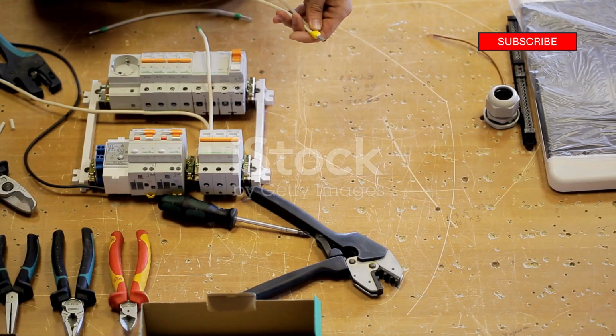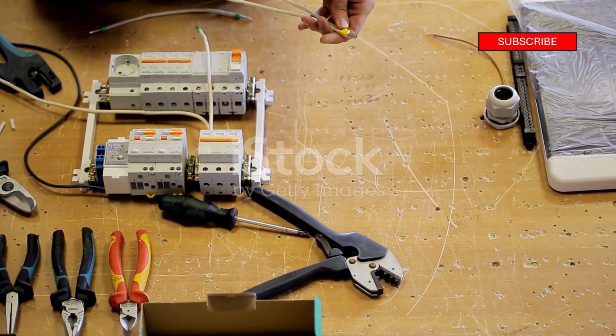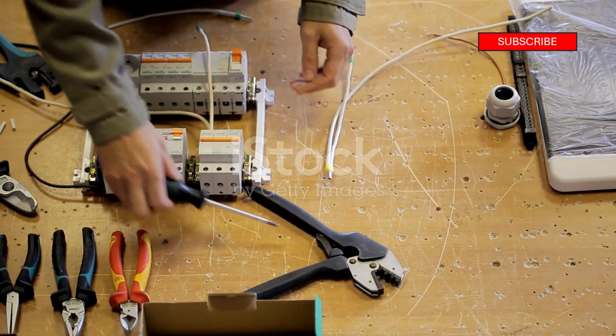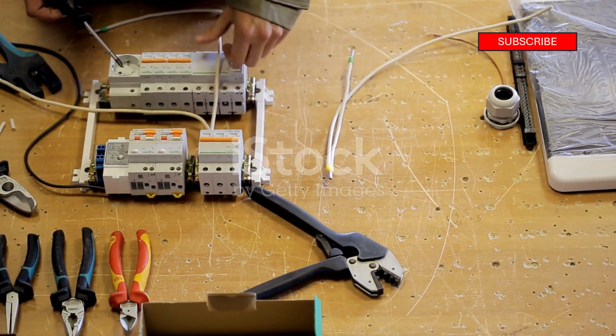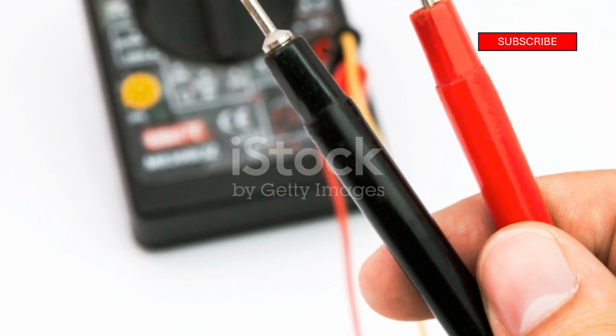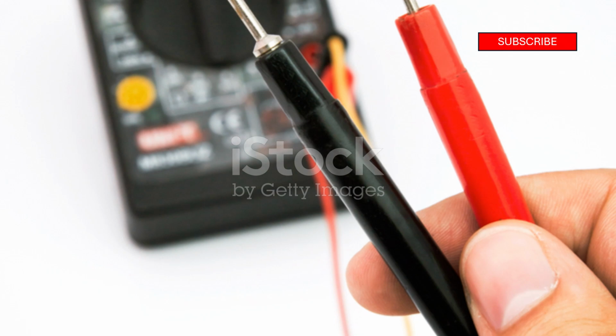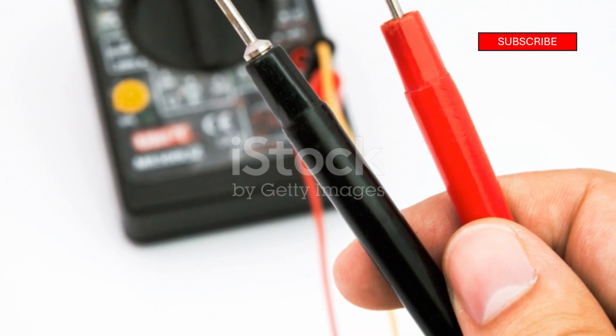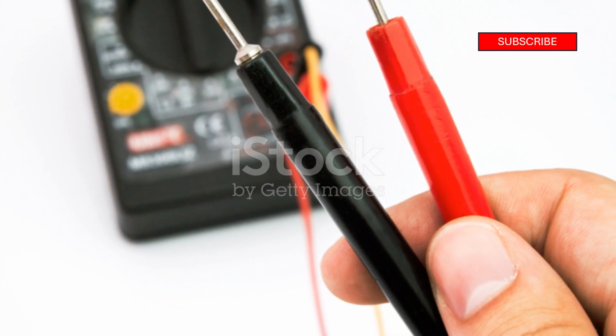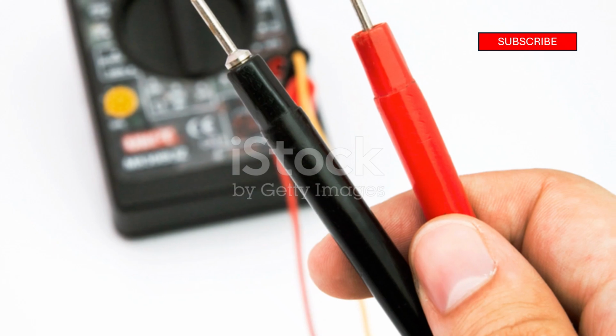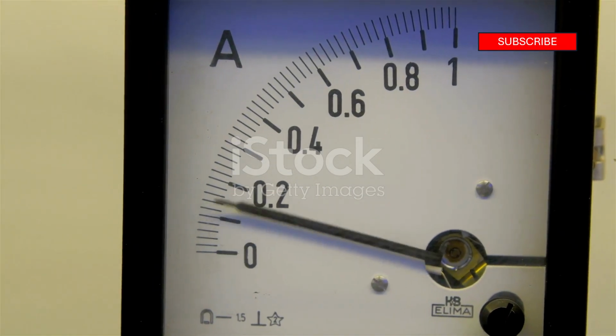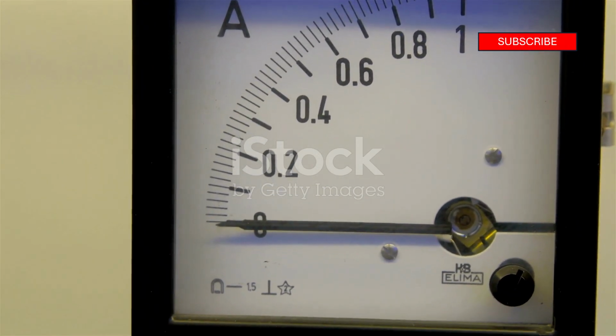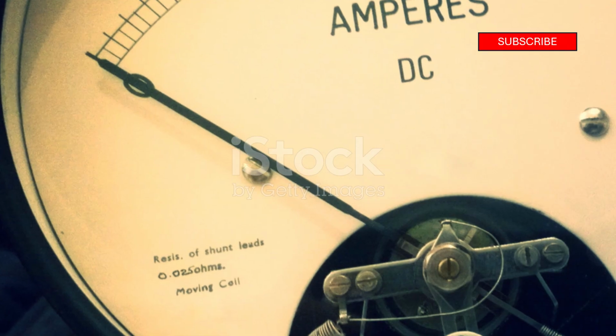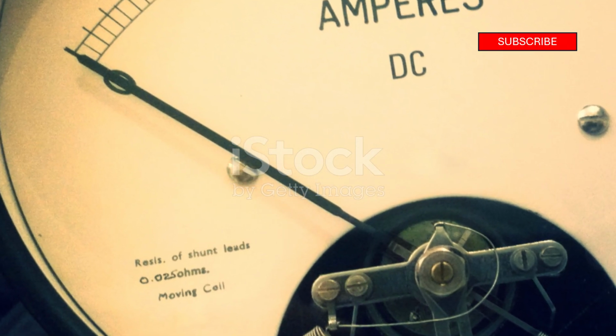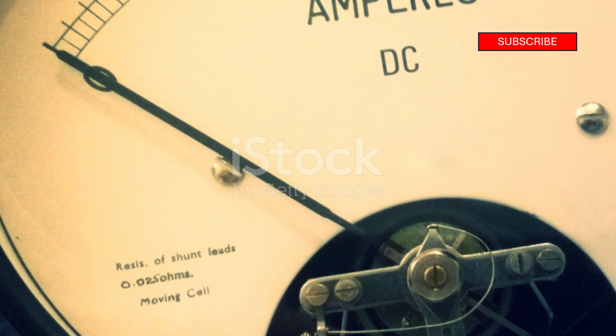To insert the multimeter into the circuit, you first need to break the circuit open, which means disconnecting a wire to interrupt the current's path. Then, insert the multimeter to bridge the gap you've created. The multimeter effectively becomes a section of the wire, allowing the current to flow through it. Before you connect the multimeter, make sure to set the dial to DC amps. Look for the A symbol, often accompanied by a straight line, which indicates direct current measurement.